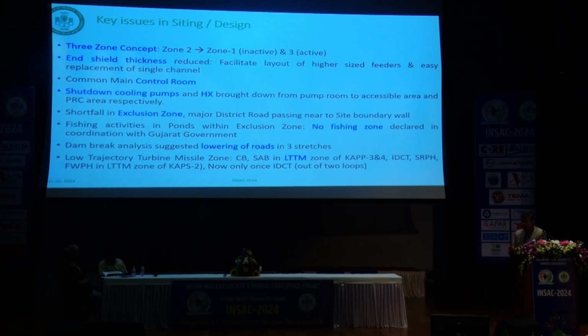End shield thickness was reduced to facilitate higher size feeders due to partial boiling and ease of replacement of the single channel. It was estimated that this reduction would increase dose inside the FM wall during shutdown and operating periods, but data collected from KAPP 3 and 4 shows the dose is 6 to 7 times less than estimated.